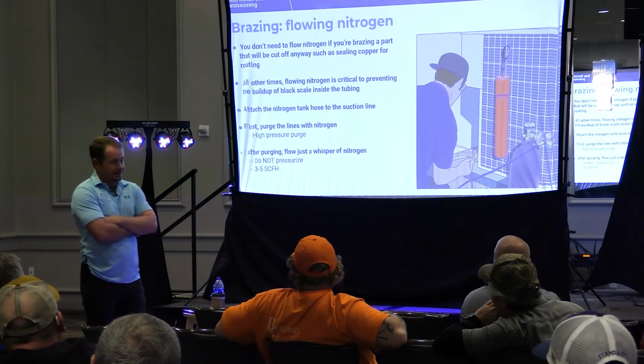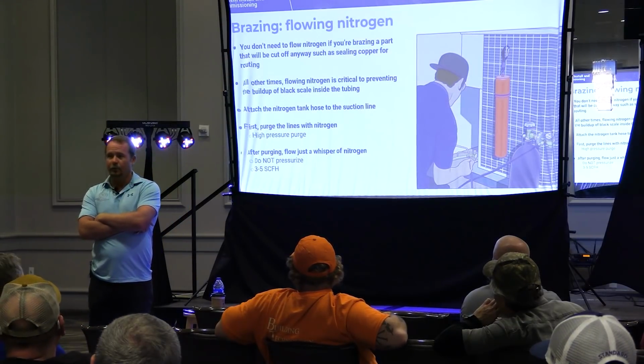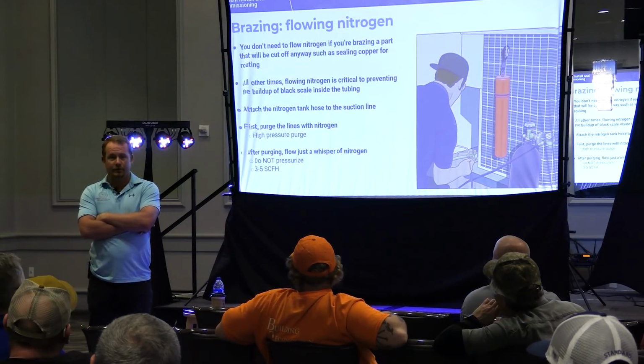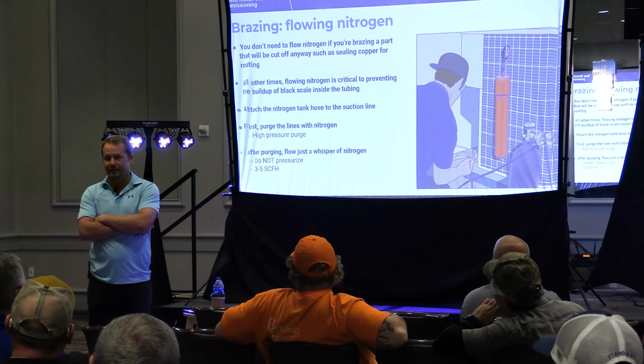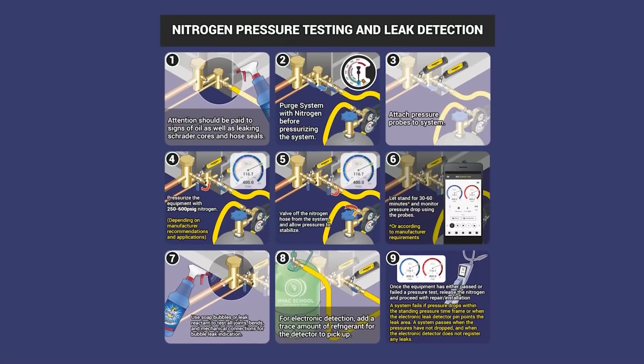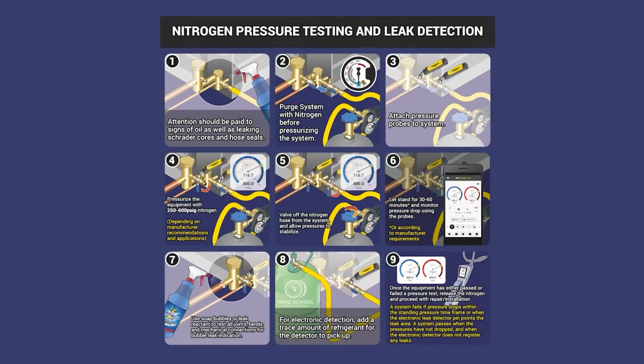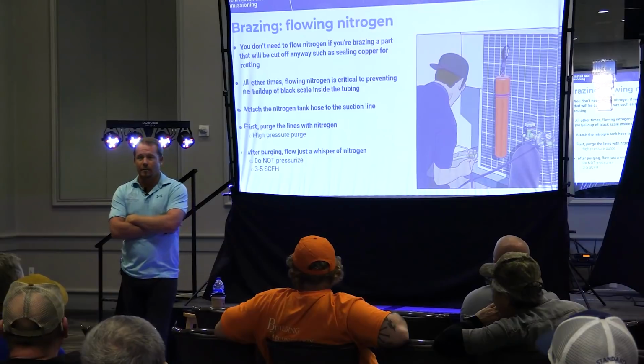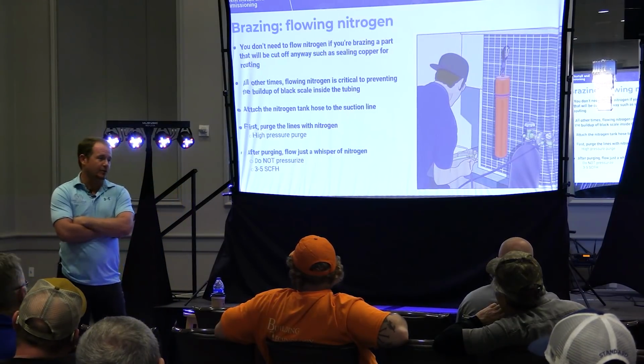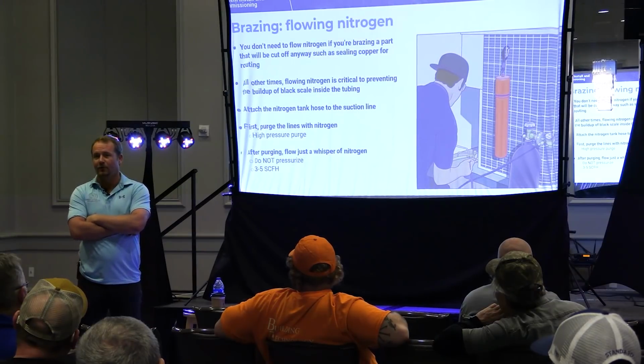The next thing they'll say is, well, I don't want to have to pull the nitrogen off my truck every time I braze. Newsflash, you're supposed to pull the nitrogen off your truck every time you braze anyway. It's called the pressure test, right? So if you're not doing that, we need to talk about that then. I also remember the days when we used to pressurize systems with R22 for our pressure test, but those are no longer the days we are in.